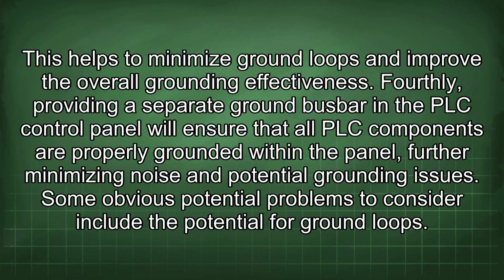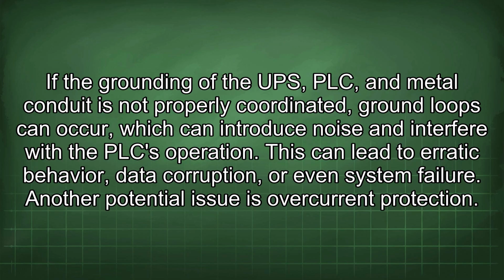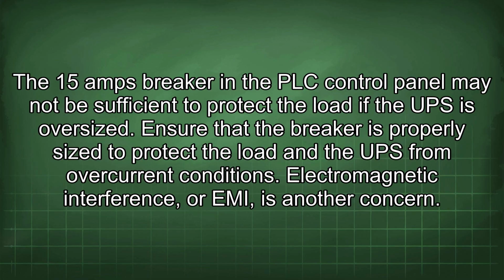Some obvious potential problems to consider include the potential for ground loops. If the grounding of the UPS, PLC, and metal conduit is not properly coordinated, ground loops can occur, which can introduce noise and interfere with the PLC operation. This can lead to erratic behavior, data corruption, or even system failure. Another potential issue is overcurrent protection. The 15 amp breaker in the PLC control panel may not be sufficient to protect the load if the UPS is oversized. Ensure that the breaker is properly sized to protect the load and the UPS from overcurrent conditions.